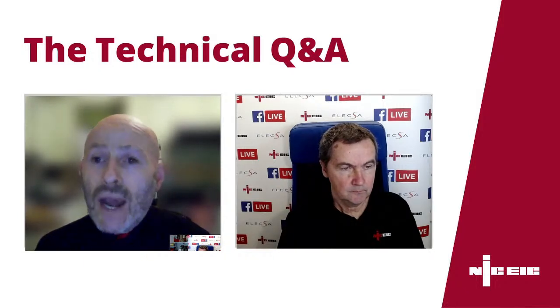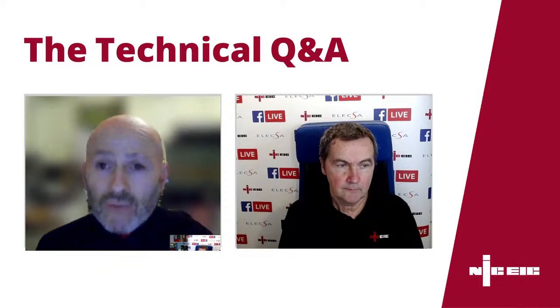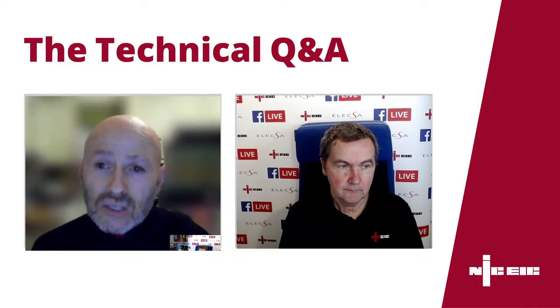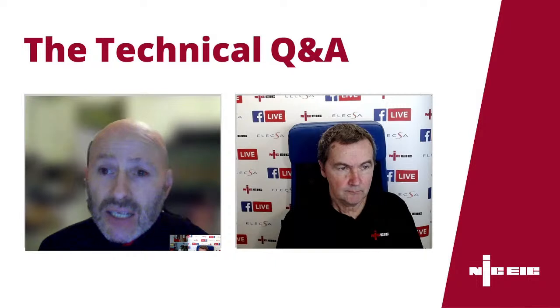And then moving on from that, obviously on the same page, you should have the access to the comments on existing installation section. So it's important to get some information in there where relevant. And I do have this conversation a lot of times with my contractors about what's classed as relevant information. So in this situation, you will be mentioning in that comment on existing installation that the existing consumer unit is made of combustible material, in brackets plastic if it suits better, and maybe mention on top of that it was installed to an earlier edition of BS 7671 and it has been verified to be adequate for continued use.